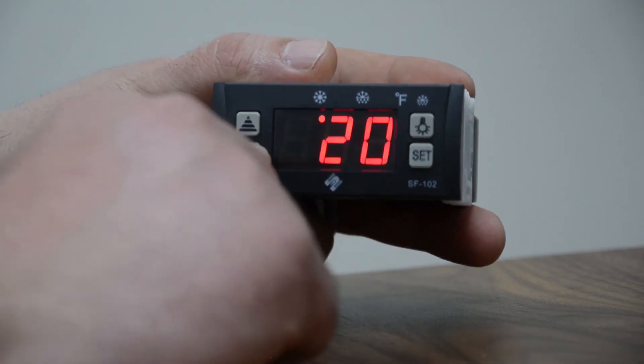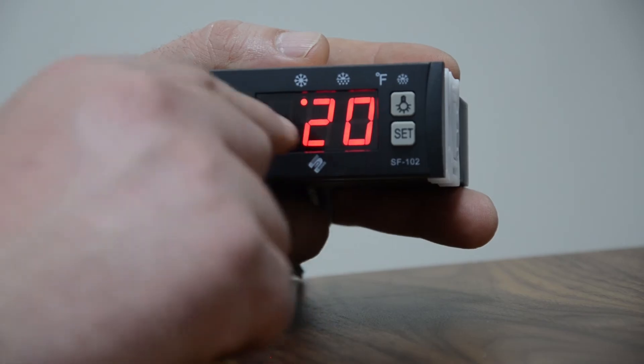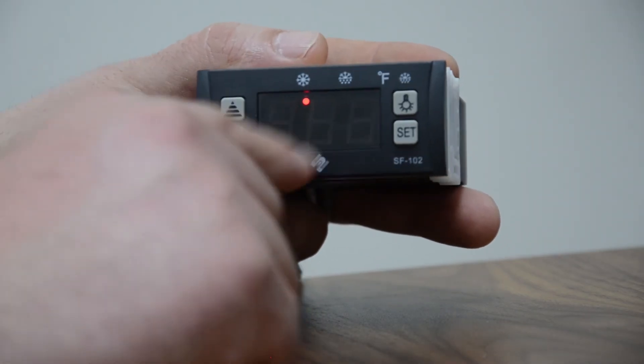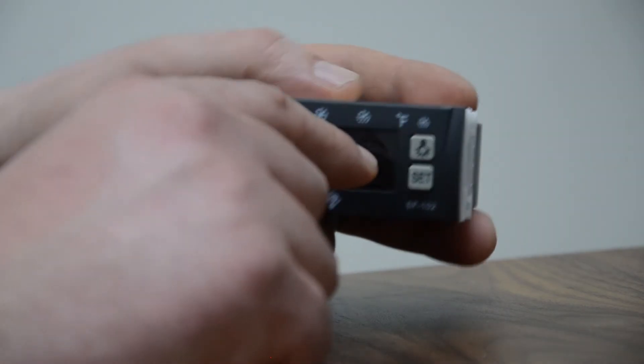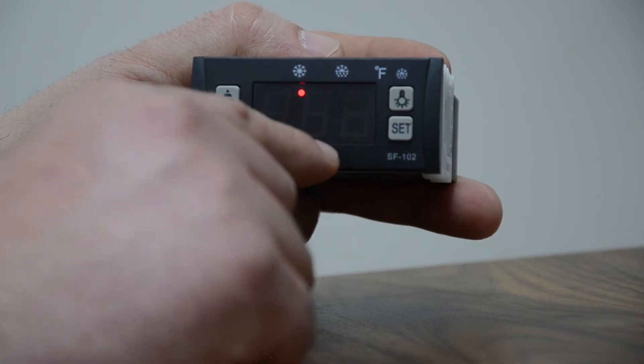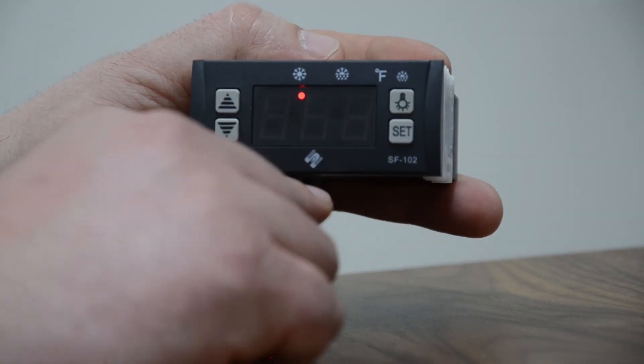F1 is the max defrost duration. We set normally for 20 minutes, which it's set for. 20 to 25 minutes is preferred. The reason why the longer you want is because you want to make sure that all the ice that's built up in the evaporator is gone, so it doesn't ruin the compressor.